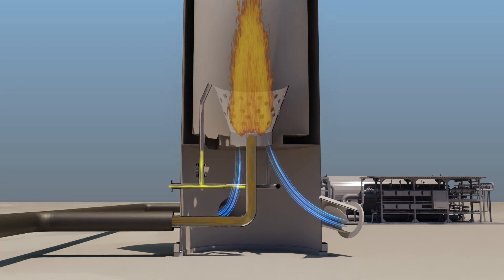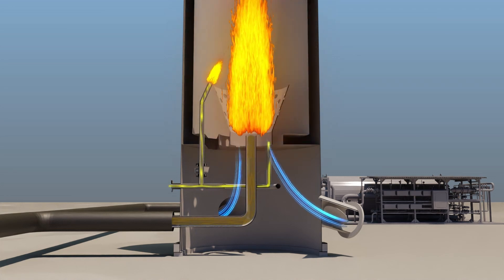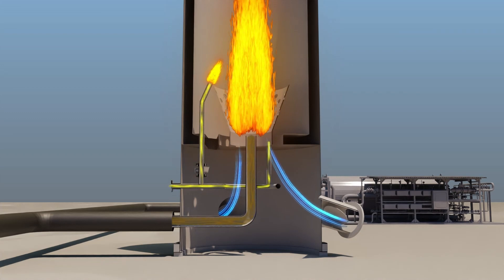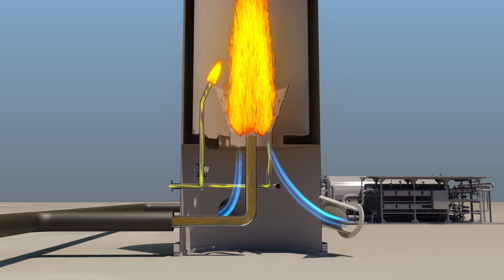To compensate for the cooling effect of those inert gases, a significant amount of additional supplementary fuel like natural gas is required to maintain the necessary operation temperature in the oxidizer.